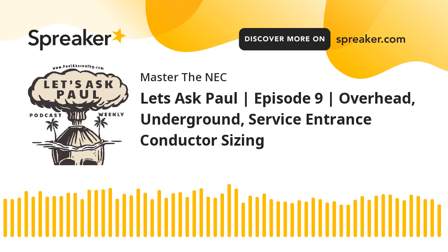So, kind of wrapping this up, I gave you everywhere that you need to be in order to size your service. Again, nothing's going to take the place of doing a calculated load. You're going to have to calculate it. But if you're sizing the conductors and you're dealing with overhead service conductors, again, go read the definition, and that's what is applicable to your situation. You're going to be looking at 230.23, size and ampacity. If you're dealing with underground service conductors, you're going to be in 230.31 for sizing. Follow the rules accordingly.